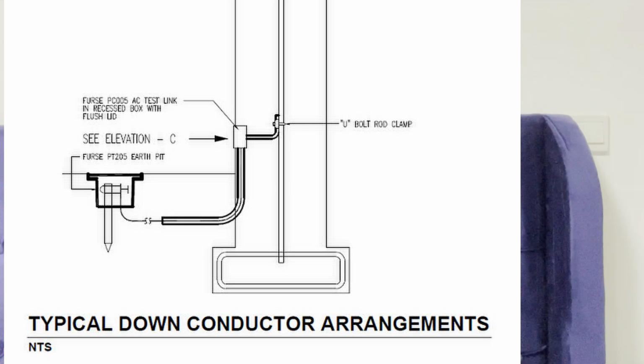If you don't do that, no worries - you'd have to run a tape on the outside of your building down to the earth termination, as we talked about in the other video. In that scenario, all you have to do is paint the tape the same color as your building, and you'll barely notice it. But if you can do it at the beginning, tying it to the structural rebar, that is absolutely perfect.